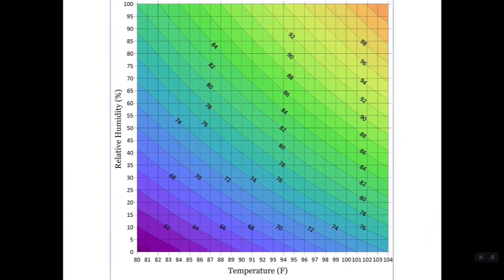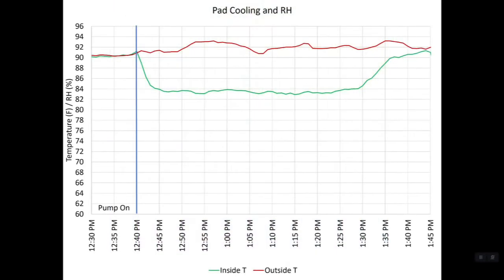We take this information and with this chart we draw a line up from 92 degrees over to 62 percent humidity, and we see the chart predicts that the incoming air temperature should be around 83 degrees. On this graph you can see we did have an incoming air temperature of right around 83 degrees, showing that the chart was pretty accurate.